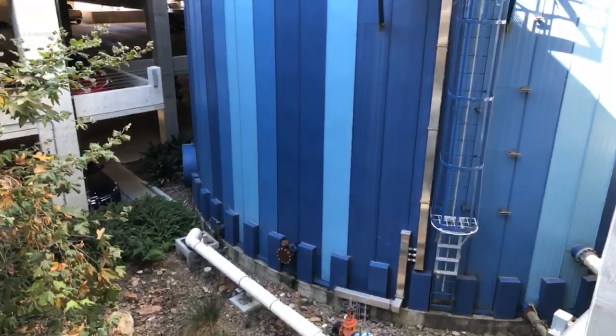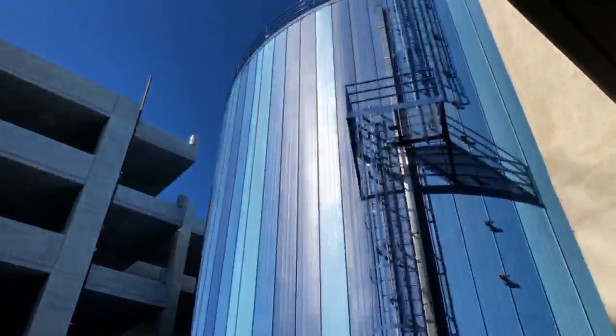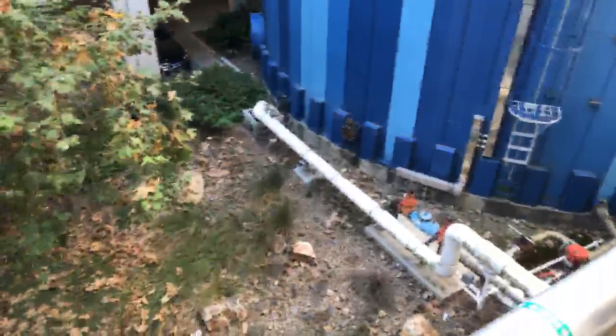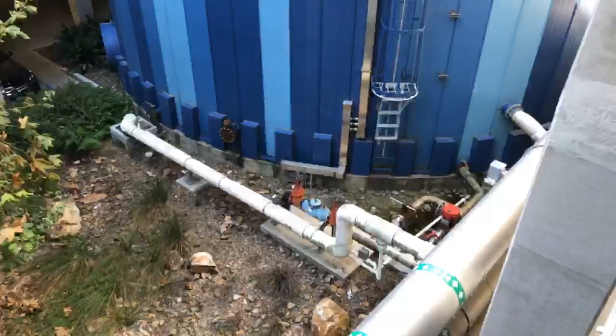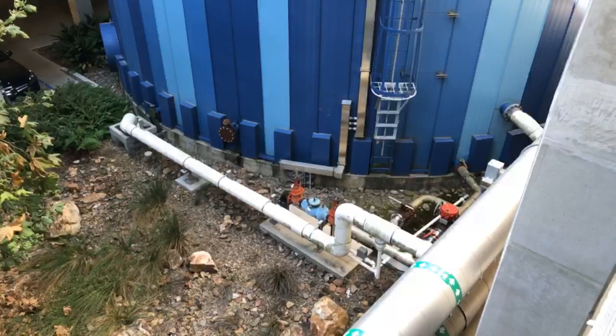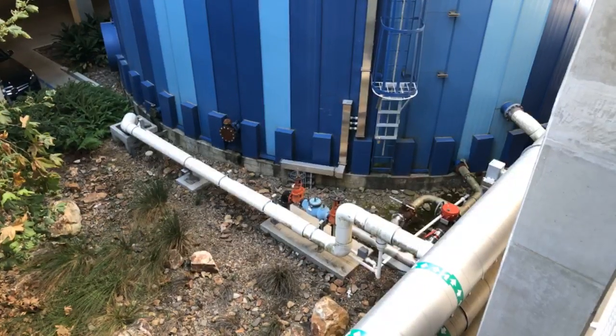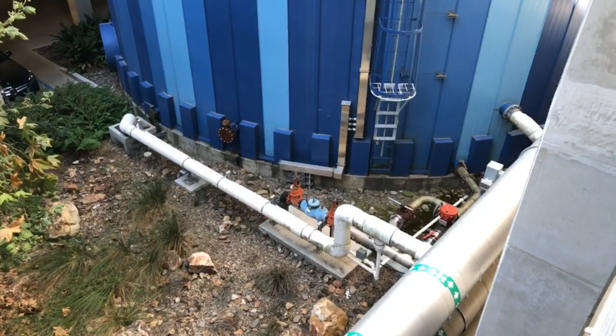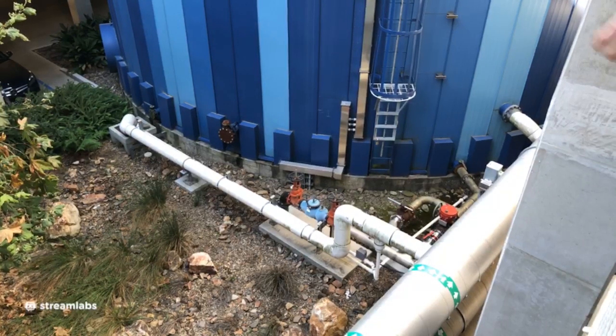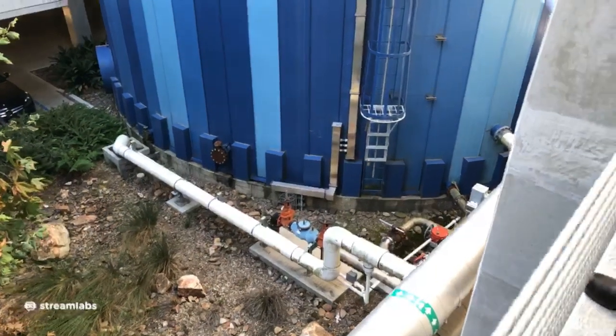There's a lot of insulation. That white PVC pipe down there is a 14-inch overflow. Why would there be an overflow at the bottom of a tank? It's for overpressurization of one tank, or if one tank is isolated — if the automatic valve is closed on one tank, it would push all the water into the other tank. So instead of having it go out the top, it has an overflow.